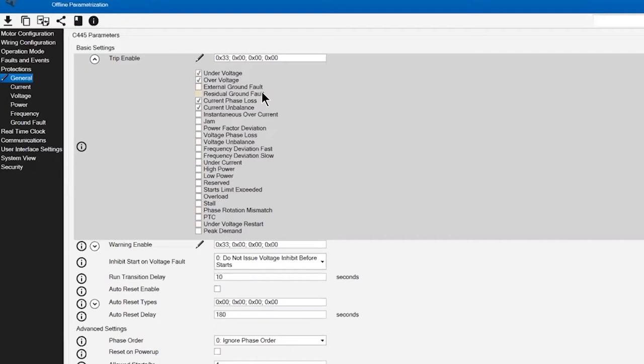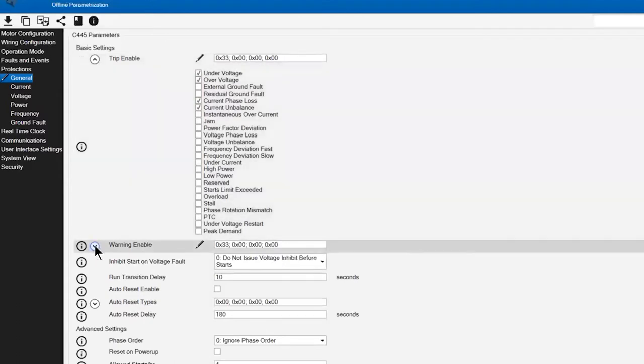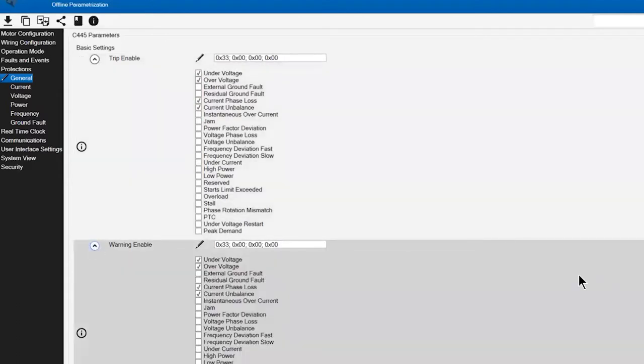I'm going to start with some basic ones that really extend reliability. I'm going to enable under voltage, over voltage, current phase loss. That's that single phase condition that can be detected—it's one of the most damaging to a lot of motor applications. I'm going to activate current imbalance.